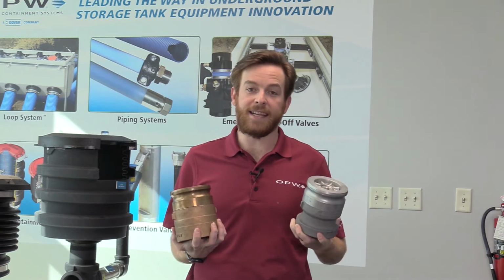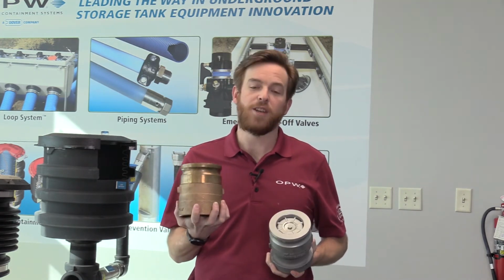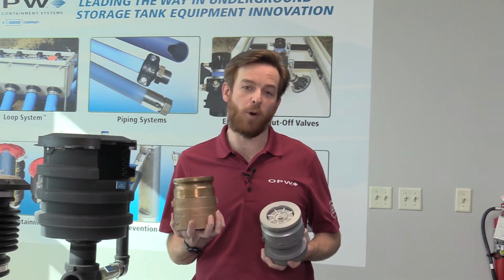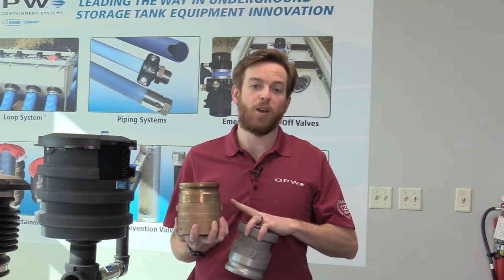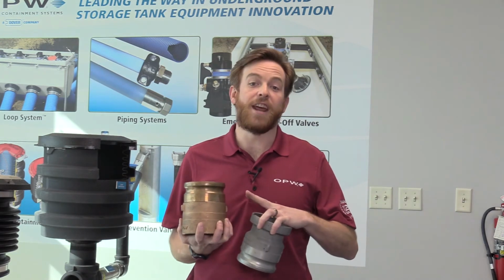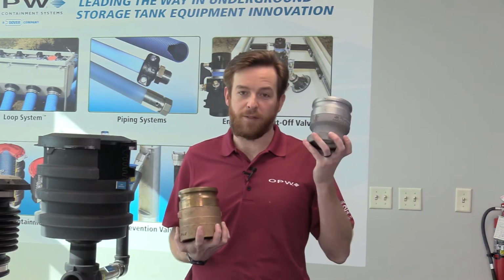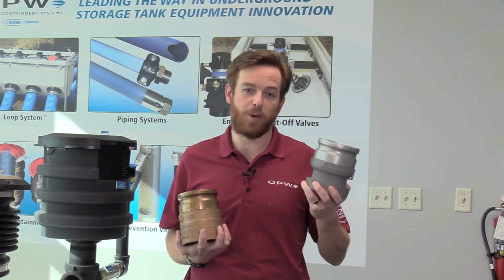In the AST, it is not required to use a vapor swivel, but if you choose to, you do have to abide by the CARB test, the TP-201.1b, and you need to run that swivel torque test when you install it, 90 days post-installation, and then every 3 years. For the 1611 AV, you just have to put it on there the one time. There's no swivel, there's nothing to test. You can put it on and walk away.